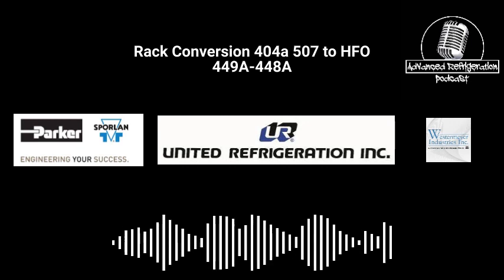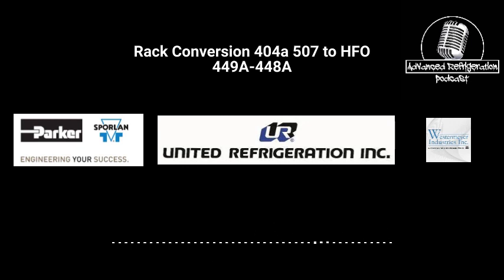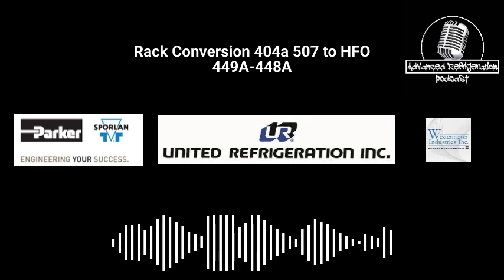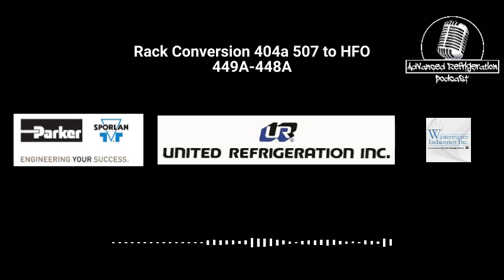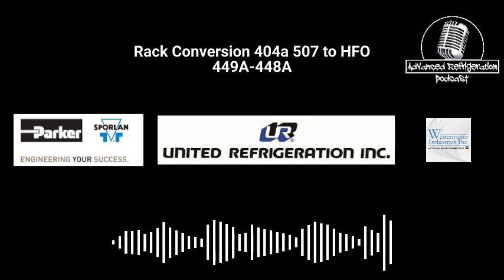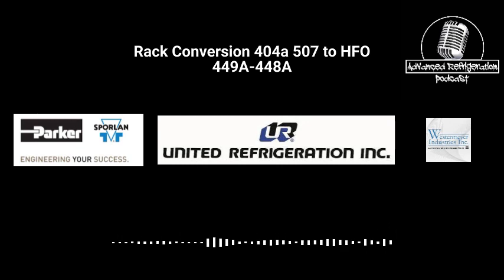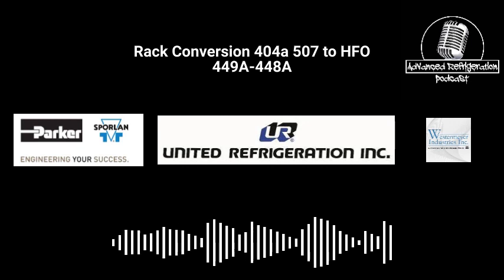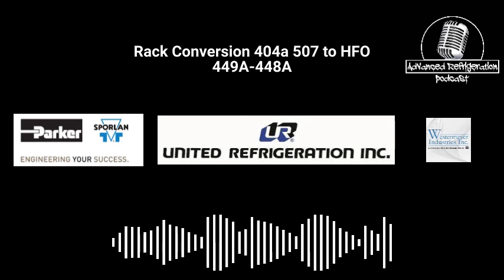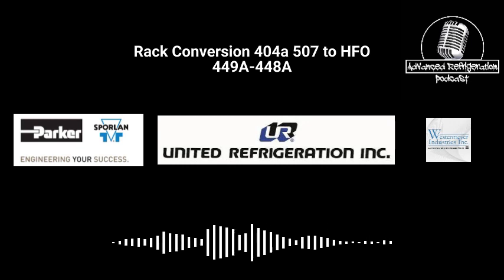So the next big thing before you do the changeover is you need to check with the compressor manufacturer to make sure, A, you're going to have enough horsepower and capacity, which you should, and B, whether you're going to need liquid injection. Whether it's Carlyle compressors getting Y1037 valves, Bitzer compressors getting BMTs installed or Y1037 valves, or Copeland compressors getting demand cooling installed, you need to check and see what you need. You need to look at whether you're going to be in that design where you're going to need the demand cooling.